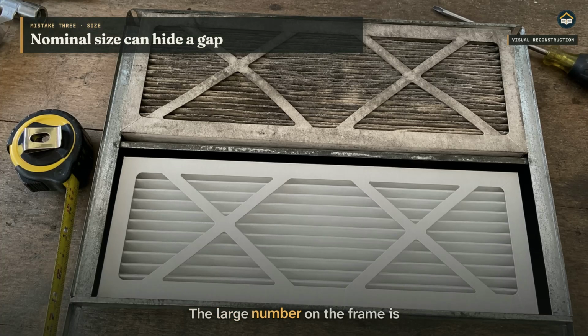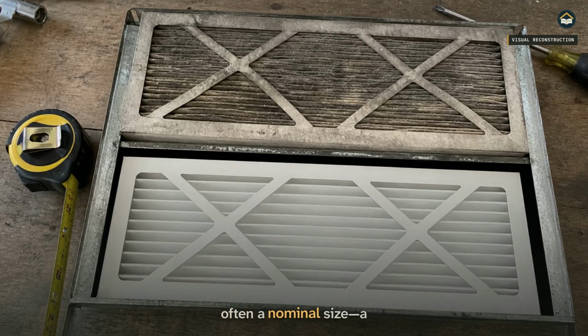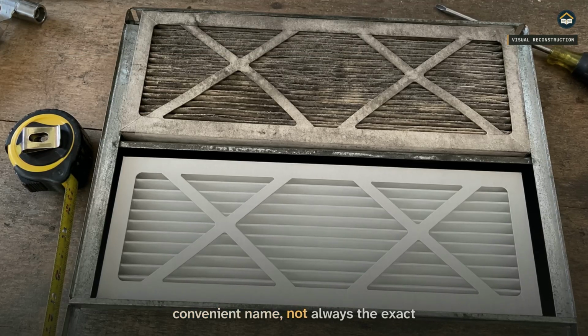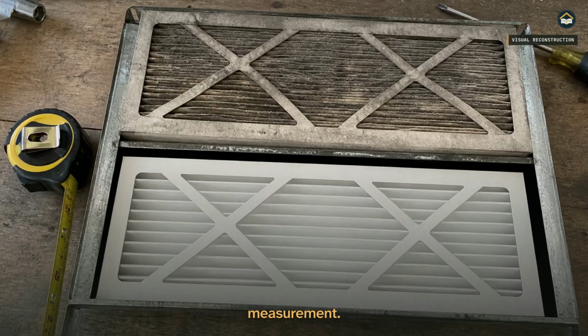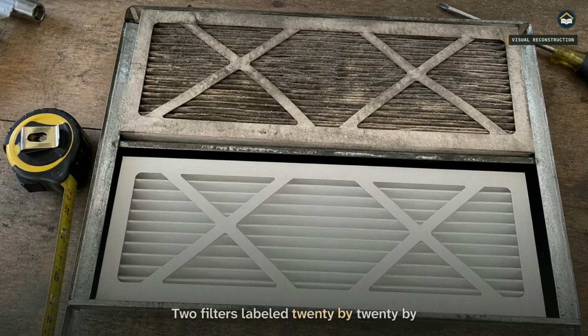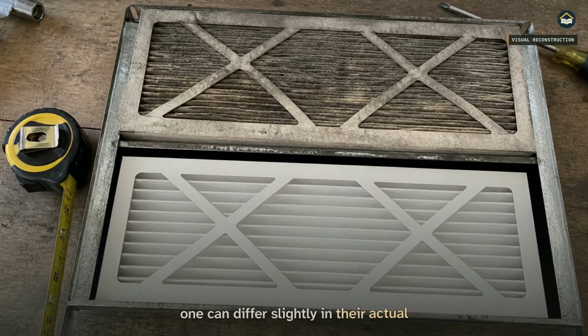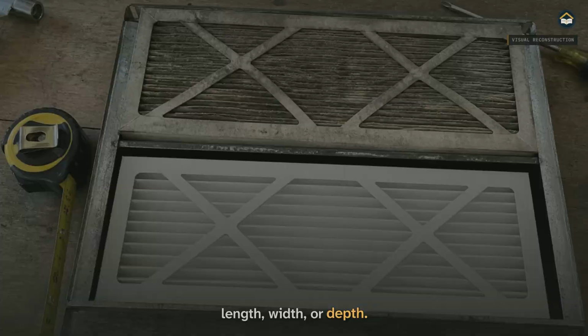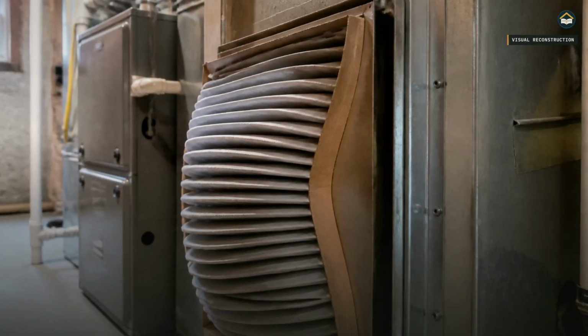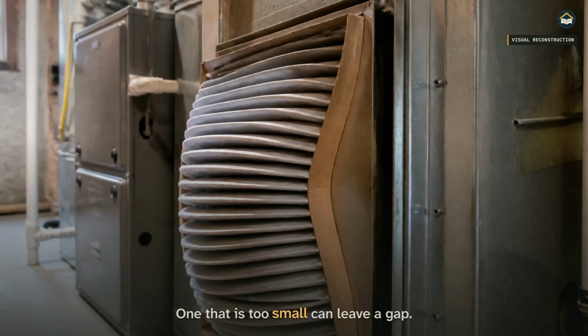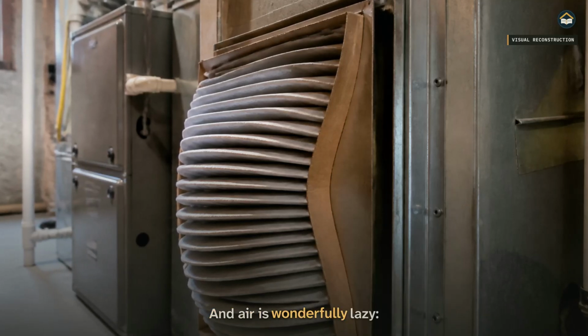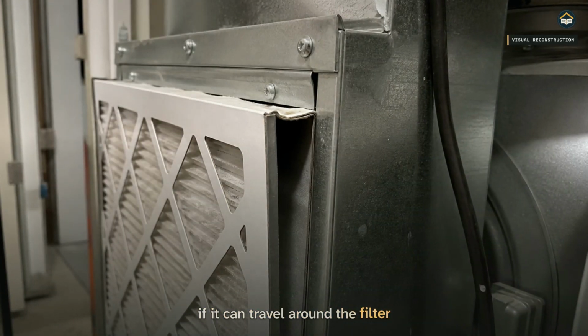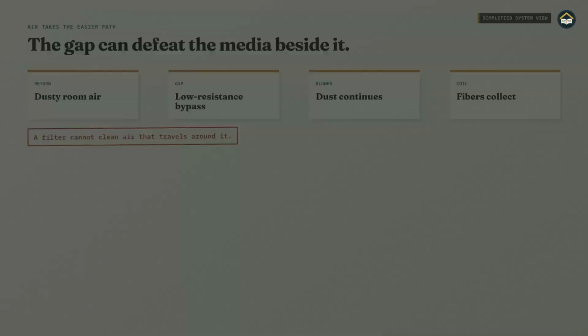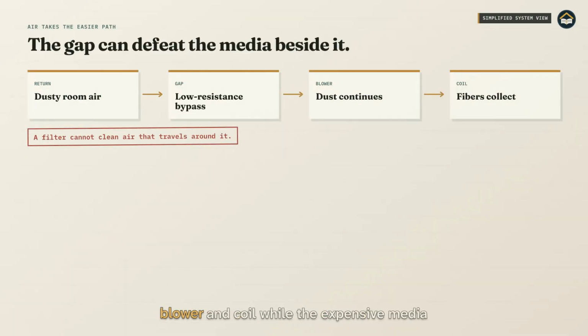The large number on the frame is often a nominal size, a convenient name, not always the exact measurement. 2 filters labeled 20 by 20 by 1 can differ slightly in their actual length, width, or depth. A filter that is too large may bow or crush. One that is too small can leave a gap, and air is wonderfully lazy. If it can travel around the filter instead of through it, it will. That bypass air carries dust toward the blower and coil while the expensive media sits beside it doing less than the package promised.